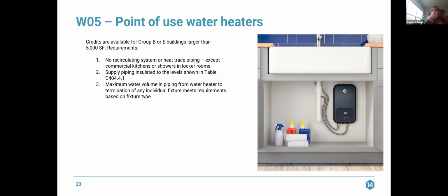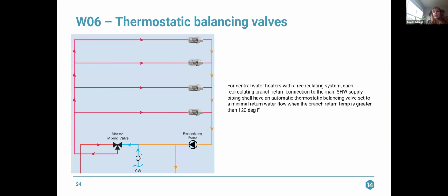And then the maximum water volume in the piping from water heater to termination of any individual fixture must meet the requirements based on a fixture type. So I believe it's like 2 ounces for a faucet, something like 8 ounces for a sink, things like that. As I should have said lavatory instead of faucet. W06, cruising through. Thermostatic balancing valves.